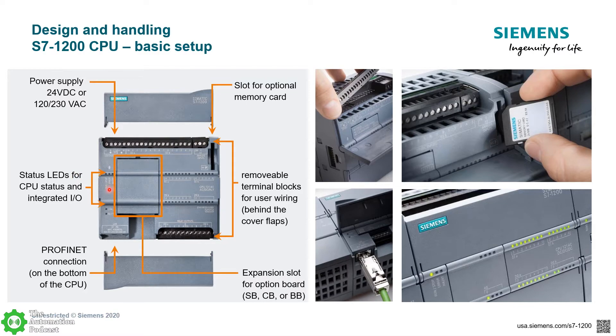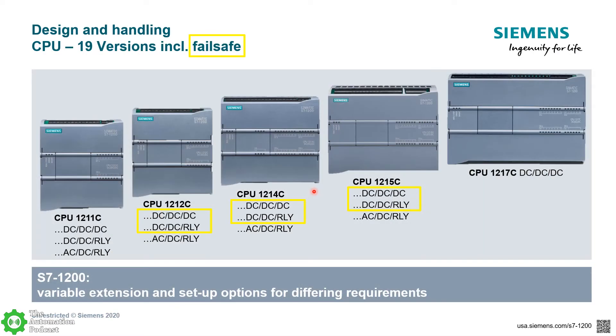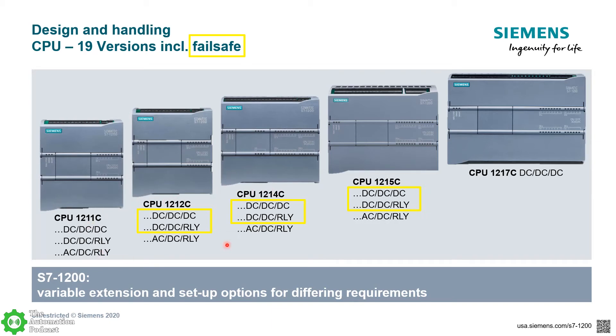There are really just five different models of the 1200, each with different configurations. The yellow box indicates the fail-safe versions: safety variants are available on the 1212, 1214, and 1215 — not the 1211 or 1217. Another configuration option is the ability to wire 120 volts AC directly into the CPU for power. For digital outputs, you can choose between 24 volt DC discrete outputs or relay outputs.